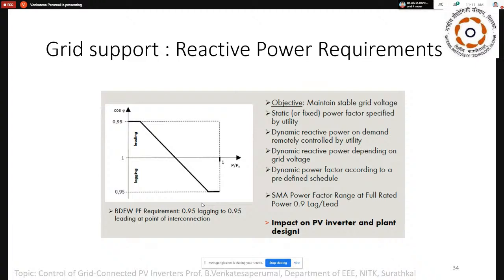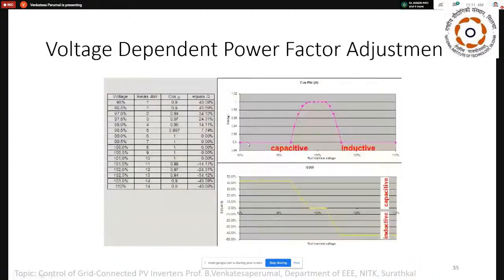What exactly does this indicate? You can see the curve, the capacitive at 0.9 going up to 1, and what is the band? You can see the voltage variation: if the nominal voltage is there, plus or minus 5%, here it is 5%, this side it is 5%, and here it is only 2.5%. So at 102.5 or 97.5, the capacitive VAR will be pushed to keep the voltage stable in the system. Voltage stability can be achieved by injecting reactive power. How much can we do? Only this much.